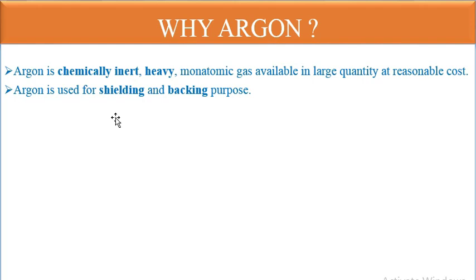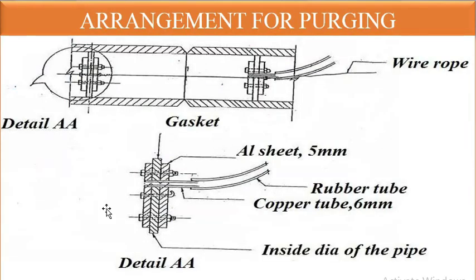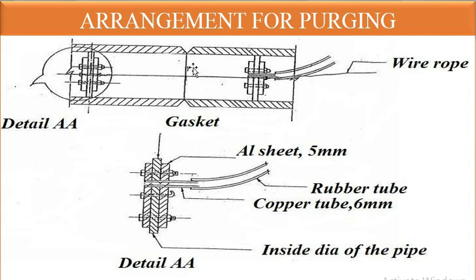The arrangement for purging: the joint is closed with an aluminium sheet of 5 mm thickness. A rubber tube carries the argon gas inside the pipe, with a copper tube of 6 mm. This blocks the air inside the pipe so that when argon fills the space, it is sealed from the outside. This is the full arrangement for purging.